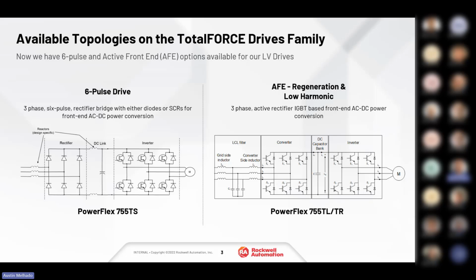Certain advantages of that allow for regen, specifically on the TR side, and allow the DC bus to be fixed and stable rather than fluctuating with the line. This creates a unity power factor throughout the entire operation or load.